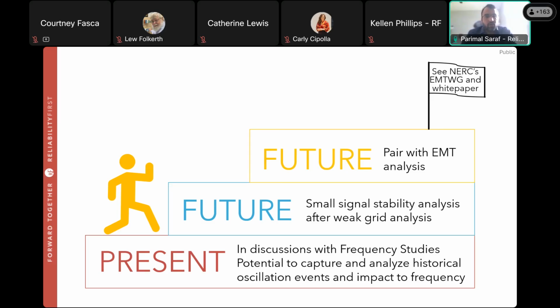That analysis provides a lot of direction into a need for EMT, or electromagnetic transient, analysis, because traditional analysis based on phasor domain tools such as PSS/E or PSLF might be lacking adequate granularity to represent a lot of these newly observed oscillatory events that are being triggered through either IBRs, large loads, or HVDC lines. So there's a lot of push towards, and need for, using EMT analysis for really observing these newly demonstrated oscillatory events on the electric grid.